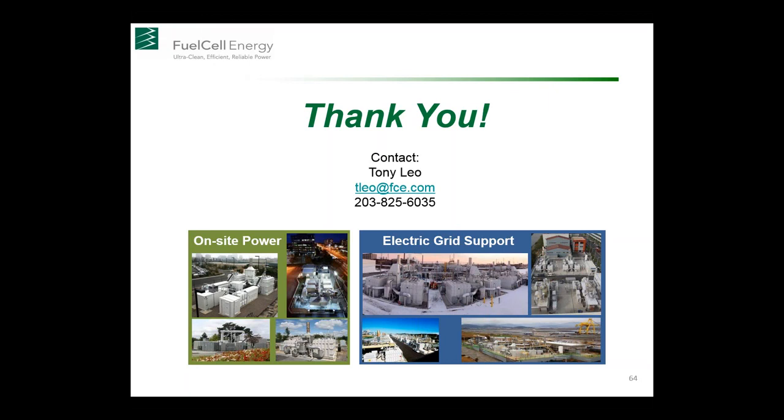But right now it's 5 years, and the way that works is that after 5 years of operation, our service people will go to the site with a whole new stack module, and we'll swap out the old module for the new one. We take the old module back to a refurbishment facility and reuse a lot of it, the manifolds and the enclosure, but we put all brand new cells in there, and that then becomes a refurbished stack module that can be used for another customer's stack replacement.